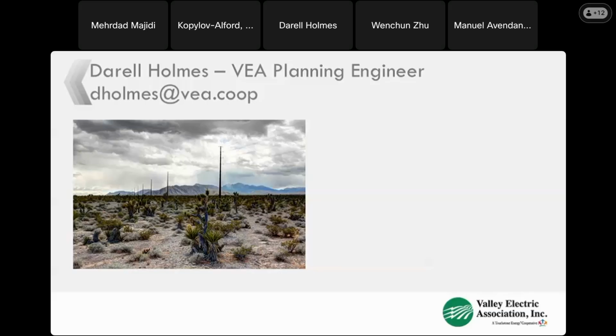Currently proposed for data center 1 is 3 230 kV substations, and then 8 or 10, a handful of 150 megawatt buildings off of that will transform down to 34.5 kV, and then to building voltage. Thank you.